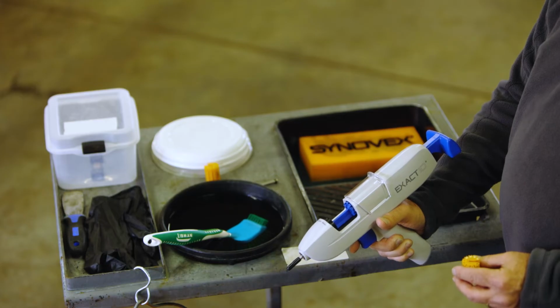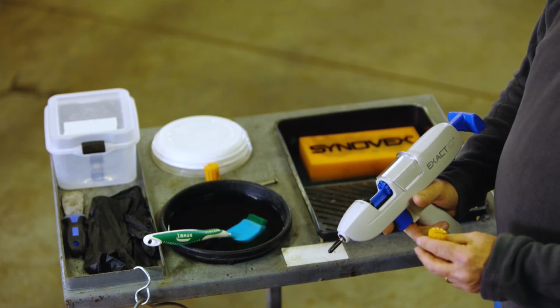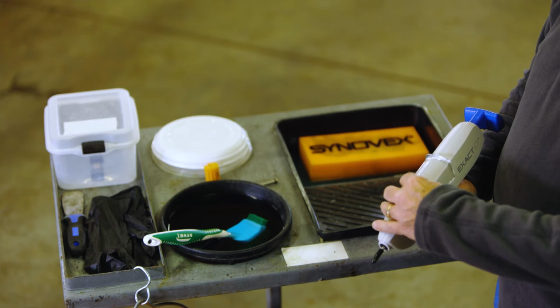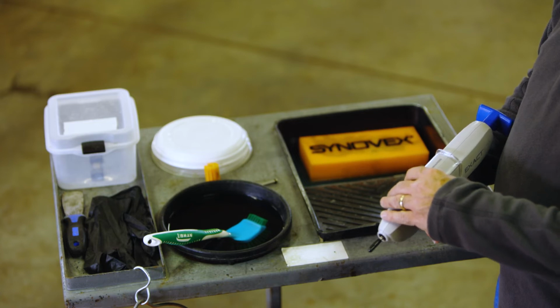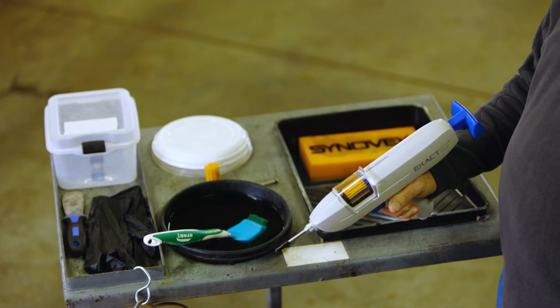When reloading a partially used clip, count the doses remaining in the clip and then reload it into the Exact10, taking care to orient the clip so that the empty dose channels of the clip are on the left side of the clip bar. Then, rotate and align the dose counter to the number of doses remaining in the clip, reclose the cover, and cock the device.